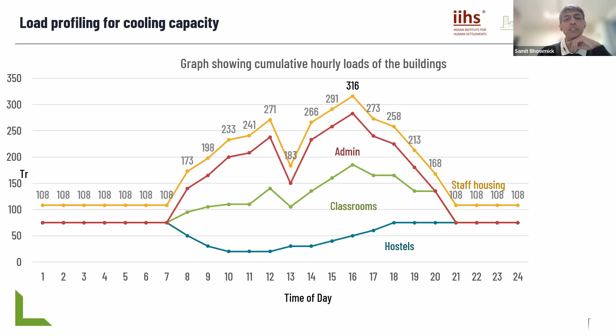So diversity is absolutely essential. We tend to always add the loads up, but very rarely do buildings operate in that fashion. So you have the opportunity of optimizing your cooling plants if you look at diversity and ask the questions that will lead you to the right cooling loads. What we gain by working on that is not only a smaller plant capacity, but obviously you're also spending less. And when we're talking about high performance buildings, this is very important, because in general people will say that whatever you're bringing onto the table is going to be more expensive, and therefore capex is important, and you should be looking at that from day one.